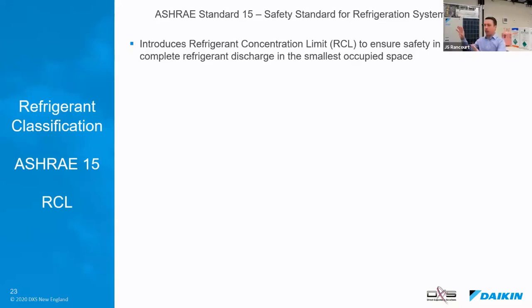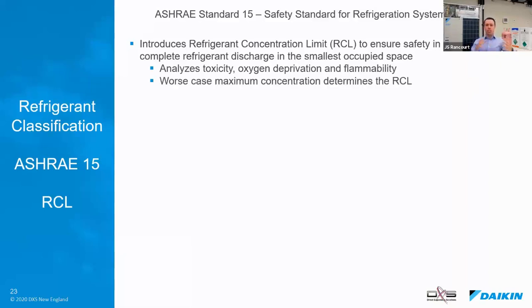And what if all of it in one system leaks in one room, in the smallest room? Is there a certain concentration amount that might make that refrigerant dangerous? It looks at: does it become toxic? Does it result in too much oxygen deprivation? Or does it have a flammability issue? And the worst case of all three of those determines the refrigerant concentration limit.